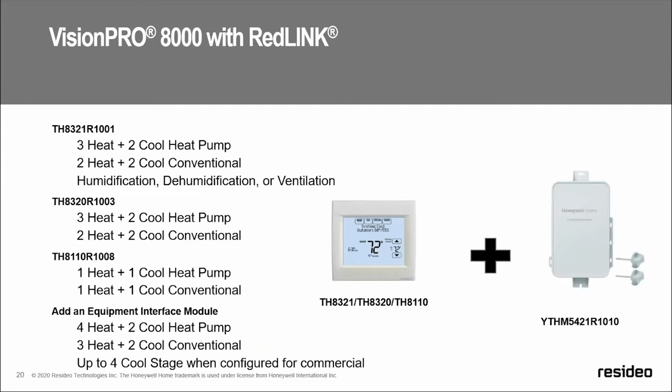Going over, we have 3 models, the most popular being the TH8321R1001. The main difference here is that it internally has a terminal for indoor air quality control and can handle one of those devices, and later I'll explain how you can move it up to 3. This is a really strong thermostat: 3 heats, 2 cools. We have the 8320R, which is the same thermostat, except it does not have indoor air quality control. And then the 8110 is a great option when dealing with zoning, which I'll get to later. If you add the EIM, the equipment interface module, we can add up to 4 heats and 2 cools, or 3 heats and 2 cools, but the 4th cool stage becomes available for our light commercial applications.